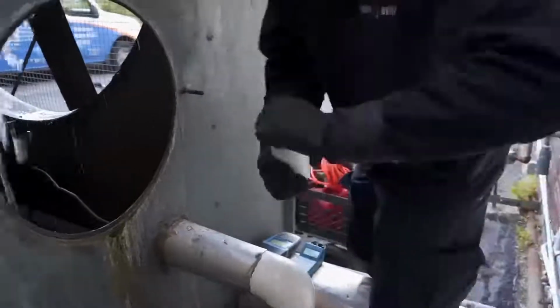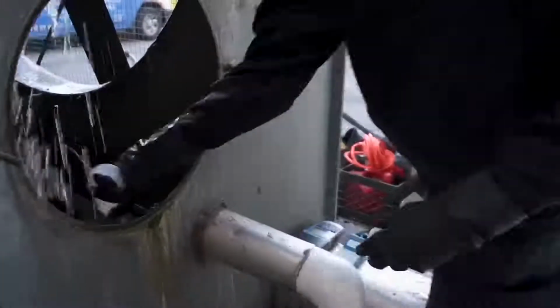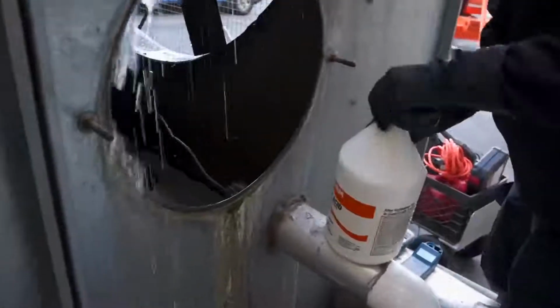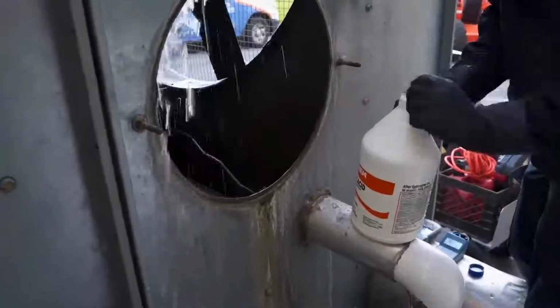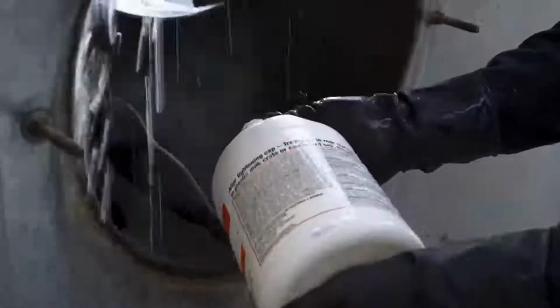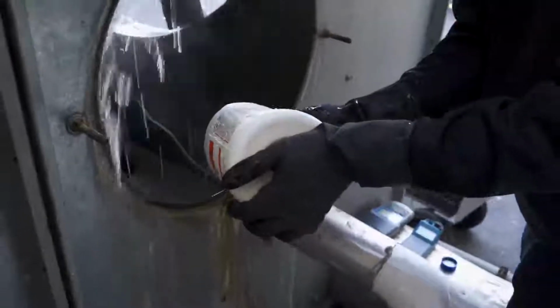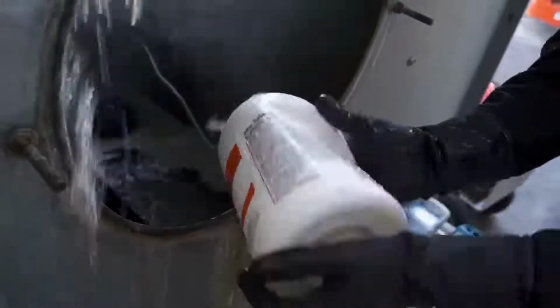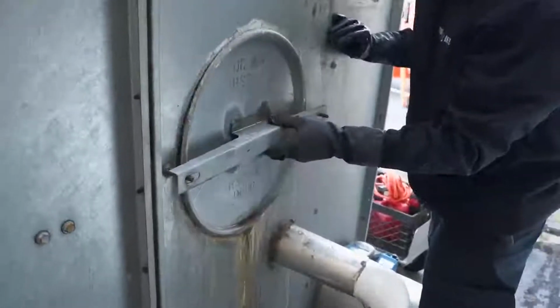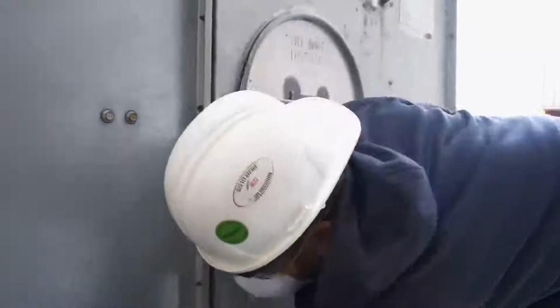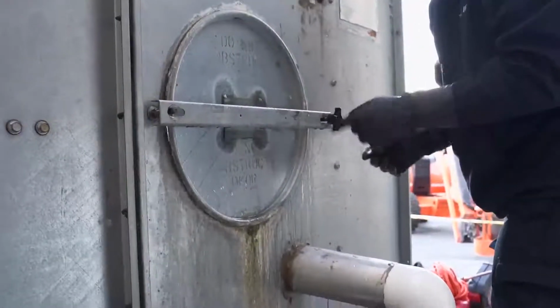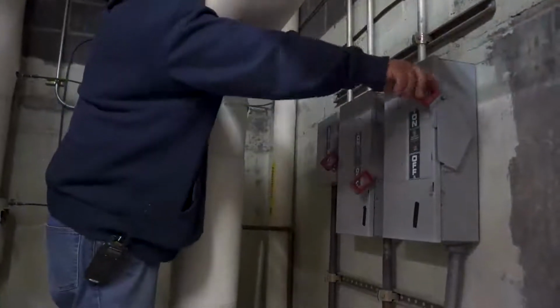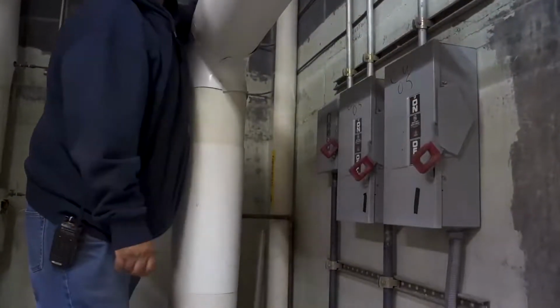Once back at the tower, add the pre-prepared chemicals to the tower basin, one at a time, making sure none of the added chemical sits on the bottom of the basin. Allow an hour for the added chemicals to circulate in the system until they are mixed completely. Also, secure the side hatch of the tower to keep the treated water inside while the chemicals are mixing within the system. After the chemicals have been fully mixed in the system, have the customer shut down the tower controls.